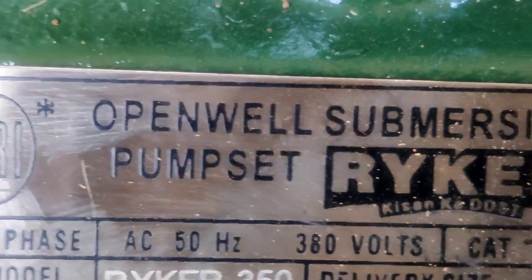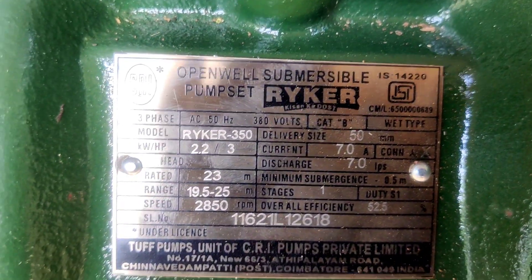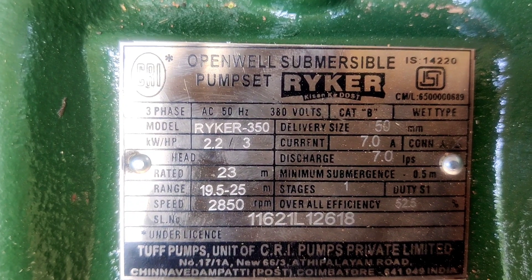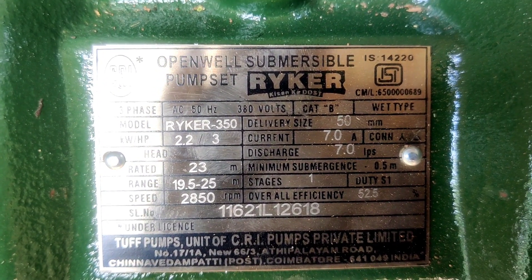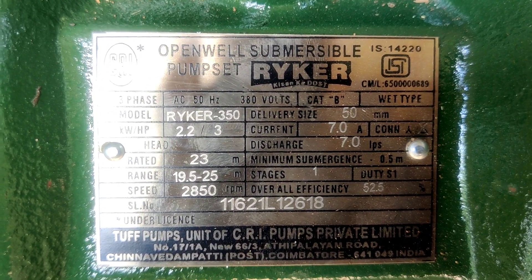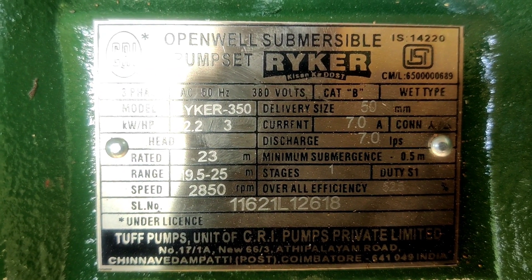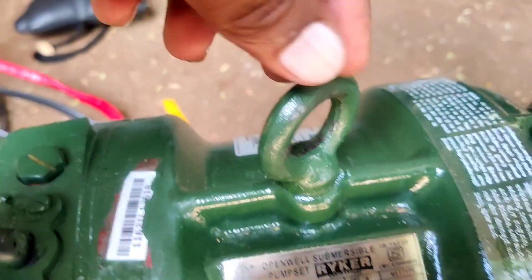This is an open well submersible pump set, Ryker model. Let's see the nameplate. HP is 3HP, kilowatts is 2.2kW, rated head is 23, range is 19.5 to 25, speed is 2850 RPM, current is 7.0 amps, delivery size is 50mm. This is blue-green color.